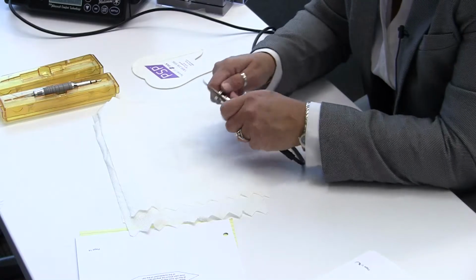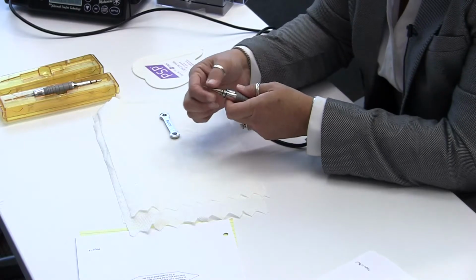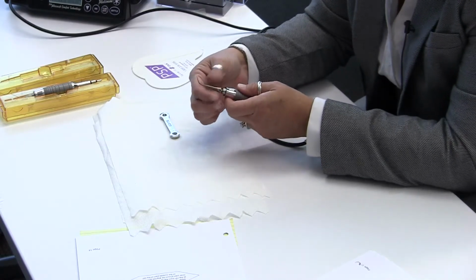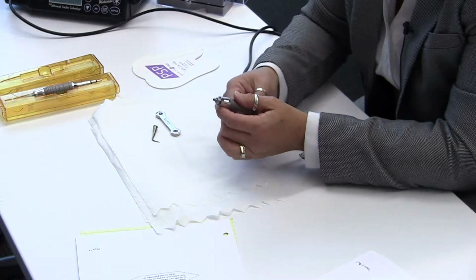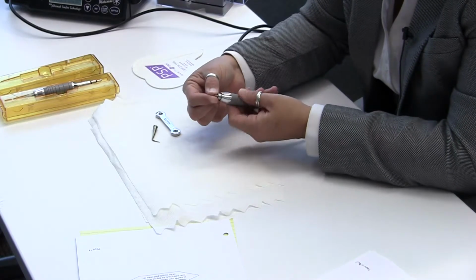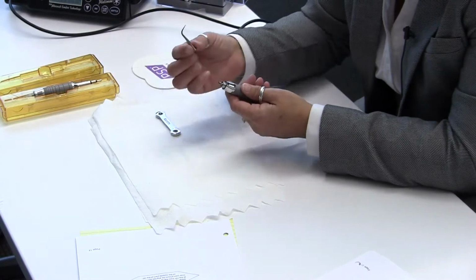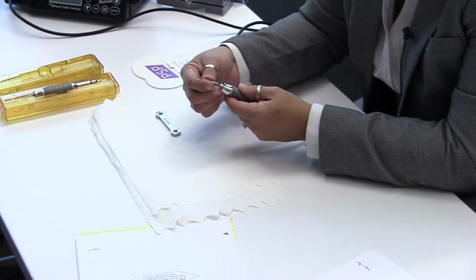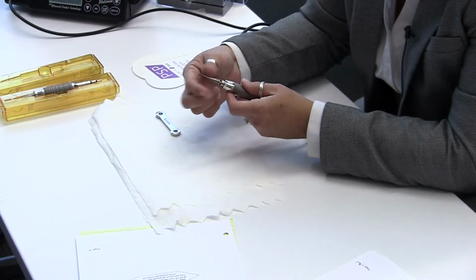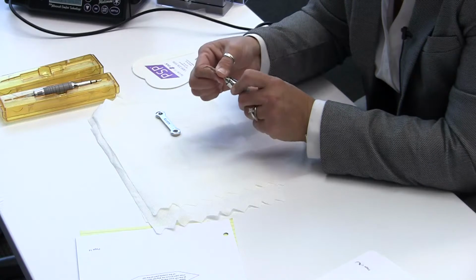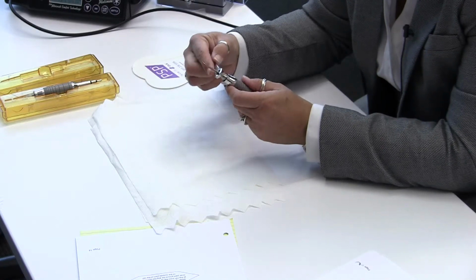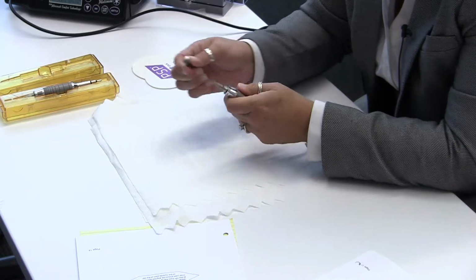We would then want to check to make sure that where the tip actually screws onto the handpiece, that mating or threading is nicely cleaned. So we would ask you to take an alcohol wipe or a 2x2 with some alcohol in it and wipe off the threads just to make sure that these are clean and that we're getting a good contact with the tip. We're then going to ask you to put the tip back on. Make sure that we finger tighten it down and that we give it 1/4 turn with the wrench, just to make sure that it's tight.